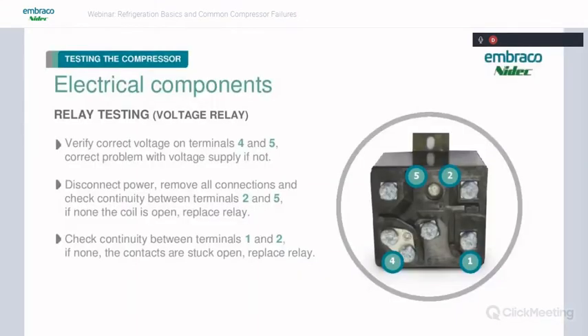The way we want to test these, you need correct voltage, and that would be on terminals 4 and 5. You need line voltage there. If not, you need to figure out why. Then we can disconnect power, remove all connections, and check continuity between terminals 2 and 5. If none, that means the coil is open, and we're going to have to replace the relay. Then check continuity on terminals 1 and 2. If none, the contacts are stuck open, because this is a normally closed relay, so we're going to have to replace the relay at that point.